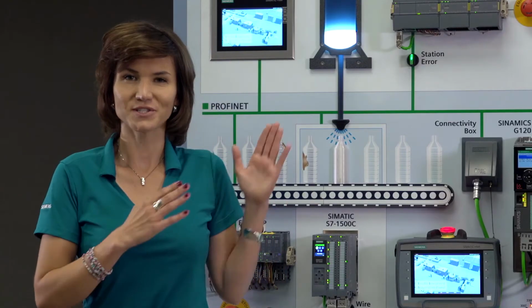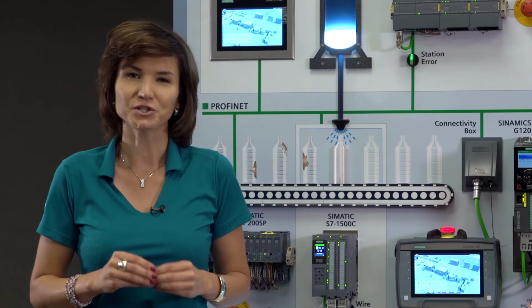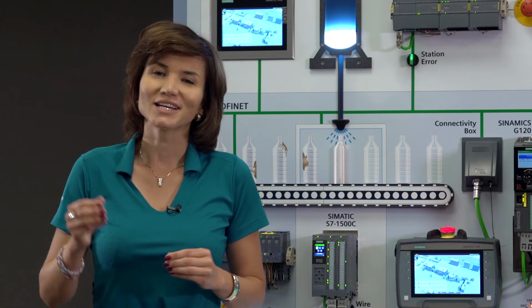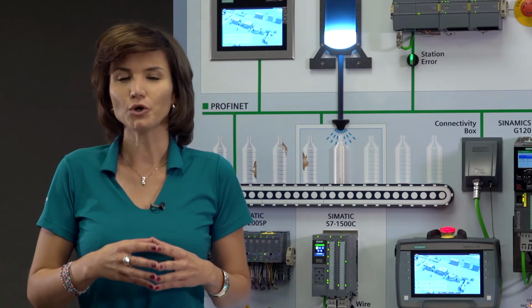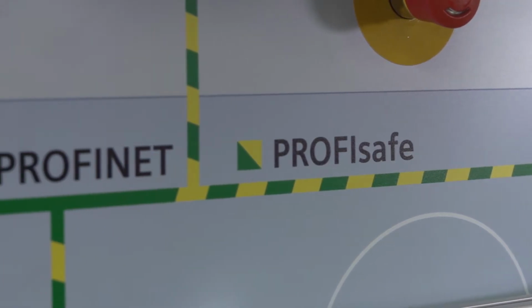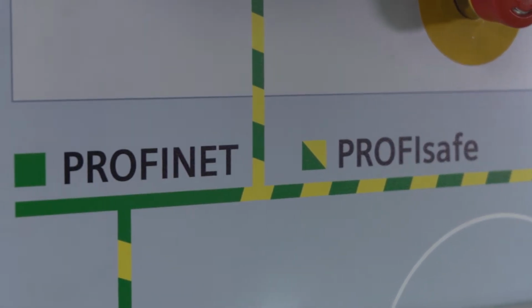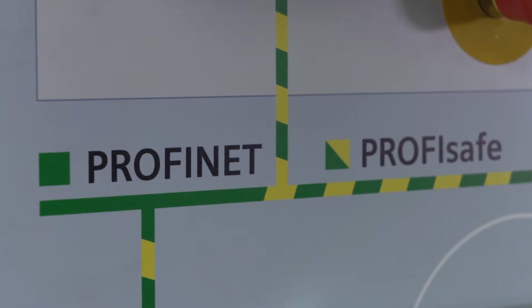Every single safety CPU has standard IOs on board. What does it mean? That you realize your safety-related task by adding safety signal modules to your CPU. You can add up to 8 signal modules, depending on the type of your controller, locally. And thanks to PROFIsafe, you can do also remote safety IOs, or as we say, networked safety. This concept allows you to cater to both safety and standard applications with just one single controller.